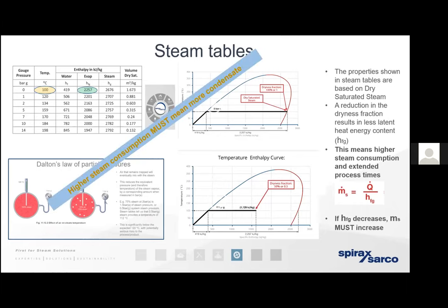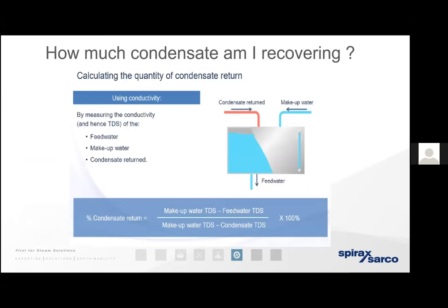A common client question is: 'I appreciate the financial benefit of recovering condensate — the benefit of reusing that sensible heat energy. The best way to reuse condensate is by bringing it back to the hot well in the boiler house.' If we're recovering condensate at, say, 80 degrees — 80 multiplied by 4.19 (the specific heat capacity) — that tells us we can recover approximately 360 kilojoules of energy for every kilogram of condensate we might otherwise miss the opportunity to recover. There's a lot of energy in that hot water.